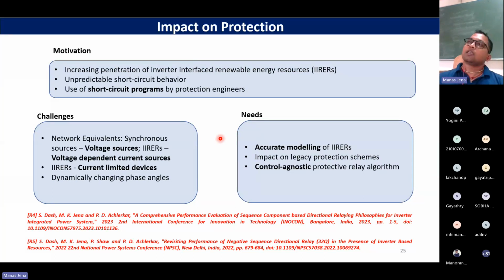Because traditionally, when power engineers came up with the protection philosophies, whether it is overcurrent protection, let us say to start with overcurrent protection, what we expect intuitively is that if there is a fault, a short circuit, we get a higher amount of current, isn't it? The source will provide a higher amount of current. So if my line, circuit or the equipment under consideration has an overcurrent relay, it will detect a fault because the current flowing through the device is more than the pickup value. So essentially a higher amount of current following a short circuit is intuitively expected.